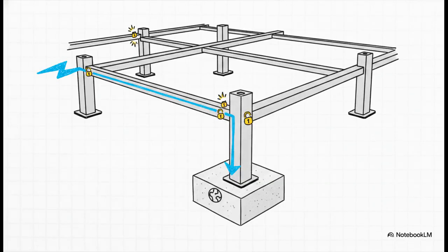Next up is Step 2. Here, stringers lock directly into the heads of those steel pedestals we just talked about. This forms a super rigid, ultra-secure grid right underneath the panels. But here is the really critical part. Every stringer carries a dedicated earthing point. They act almost like a lightning rod for static. The panels, the stringers, the pedestals, they all connect together to form one continuous discharge path that's directly wired straight into the facility's earthen grid.